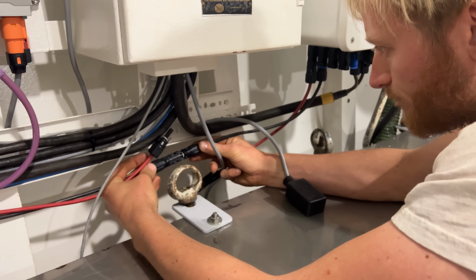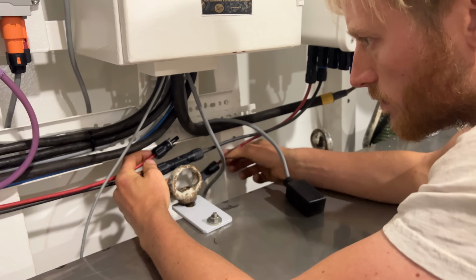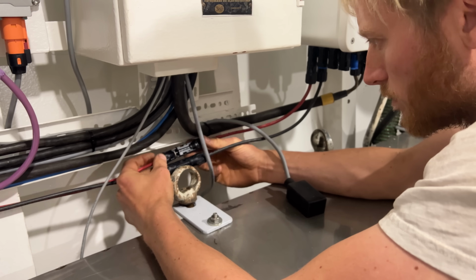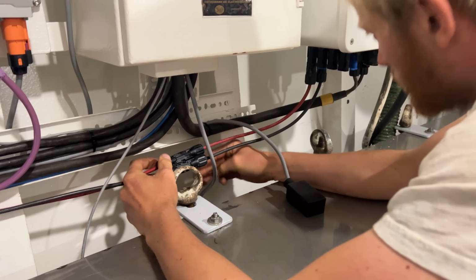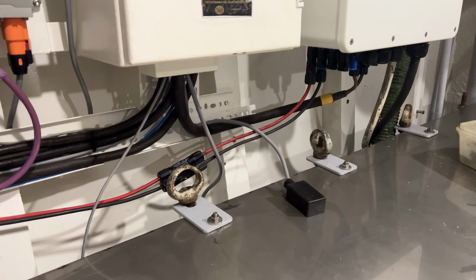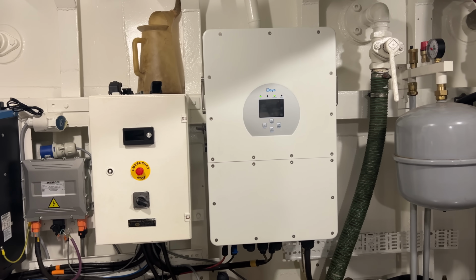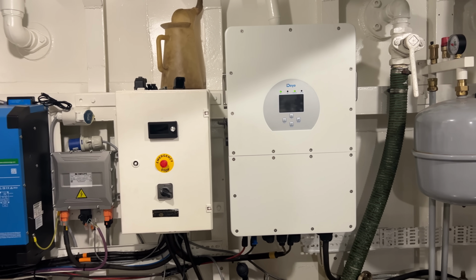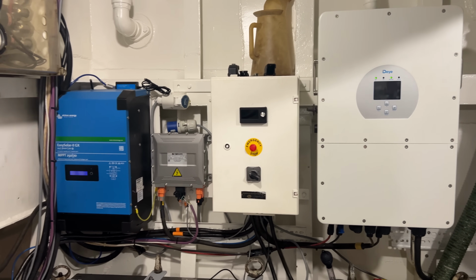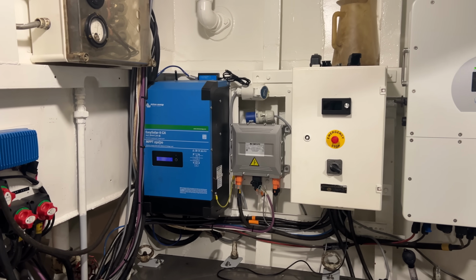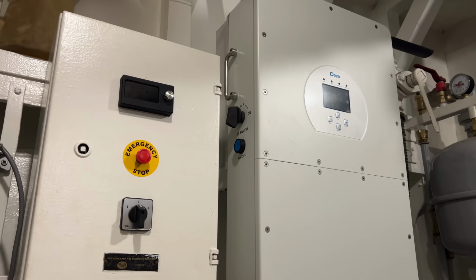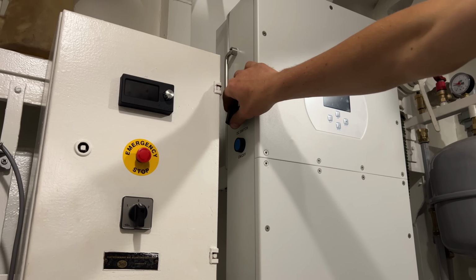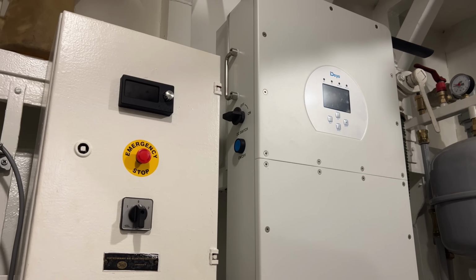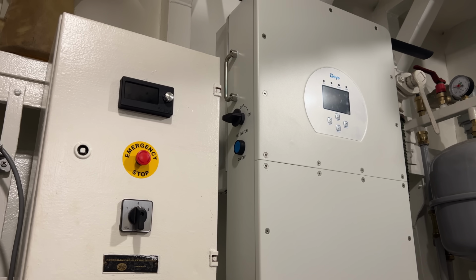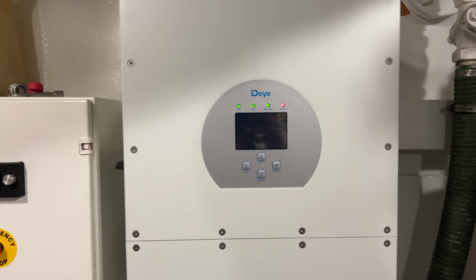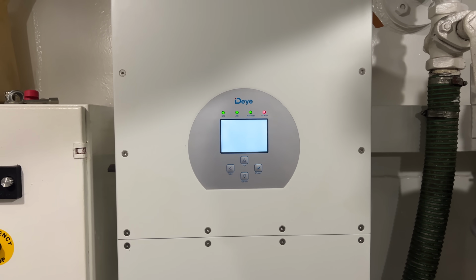Our current solar array is really at the top limit of what the Victron 24 volt solar inverter can handle. But for the new high voltage inverter, it's near its minimum. So there's a perfect band of overlap between the two. If there's ever something with the big inverter or the high voltage battery bank, we can always switch back to the small inverter and still be able to use the solar panels. The main high voltage battery switch is not on yet, but with only the solar power connected to the hybrid inverter, it can already be switched on, so I can check and change the charging and inverter settings to be aligned with the battery pack.